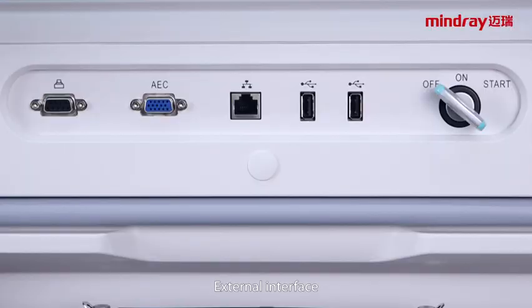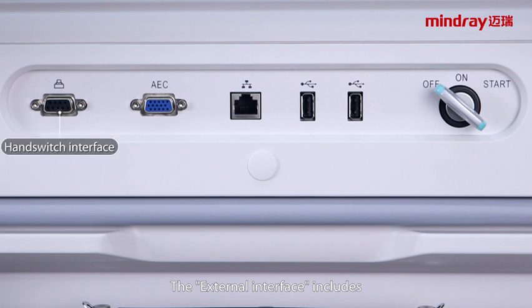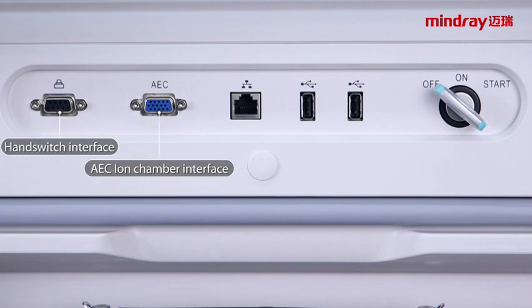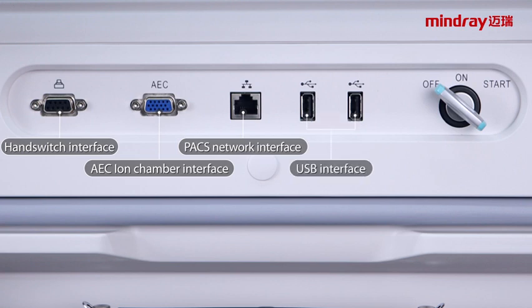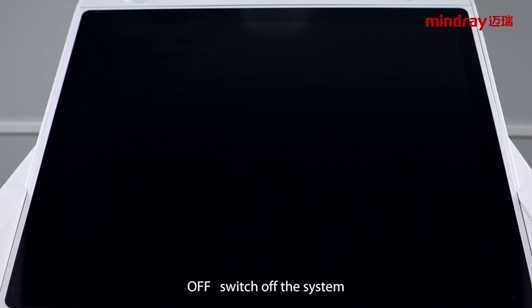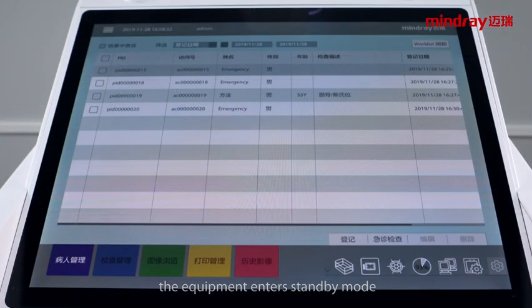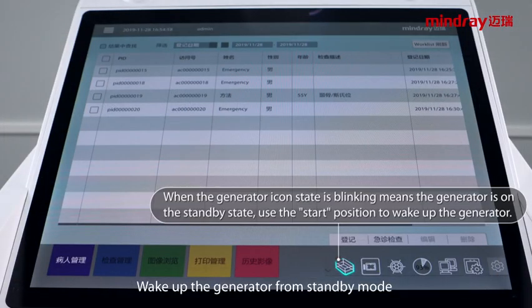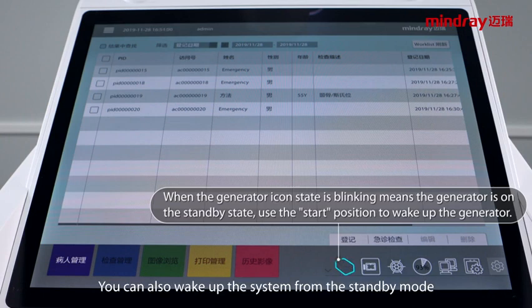Indicator, external interface. The external interface includes hand switch interface, AEC chamber interface, PACS network interface, USB interface, key switch. There are three positions of the key switch: off, switch off the system; on, switch on the system. The equipment enters standby mode. Start the system to operating mode. Wake up the generator from standby mode. You can also wake up the system from the standby mode.